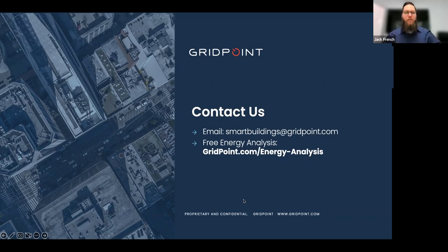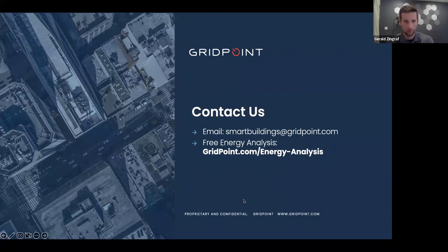I think maybe we can both answer this one. For data requirements, we need an internet connection, or some way for our controller to call home. That can be via Ethernet on site, with static IP or DHCP. We can also use cell modems if you're in a very rural area and you don't have internet on site. Power requirements, just a couple spare breakers, I think. Gerald, correct me if I'm wrong. No, that's right. Whether it's spare breakers, we can also just use a wall wart, a little plug. So if you either have an open plug or a spare breaker for us to power the system that way.